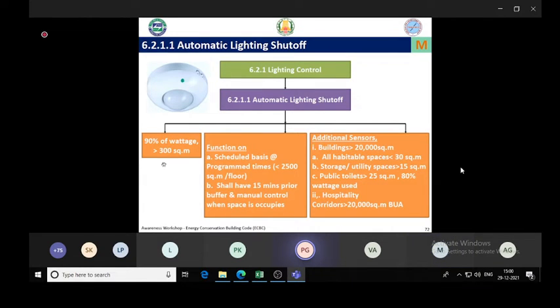Right? Then there are additional requirements for buildings more than 20,000 square meter. There should be separate occupancy based controllers for any room less than 30 square meter and any storage rooms, and public toilets more than 25 square meter, as well as corridors of hotels and hospitals. They all should have occupancy sensor based control. Okay. Not only these, plus any conference and meeting rooms in any building should also comply with occupancy sensor controls.